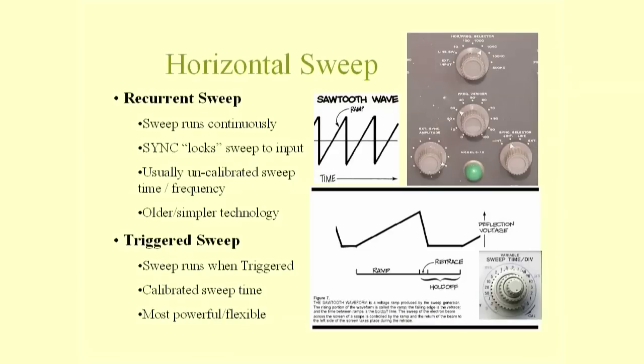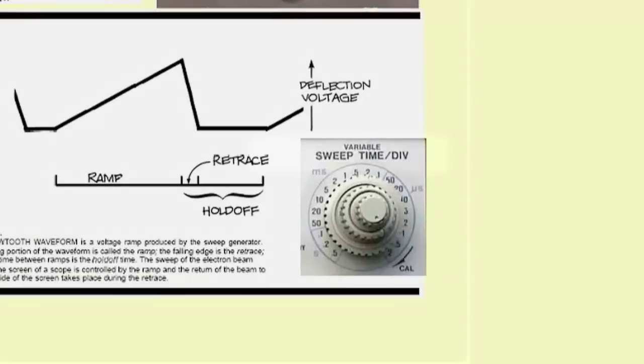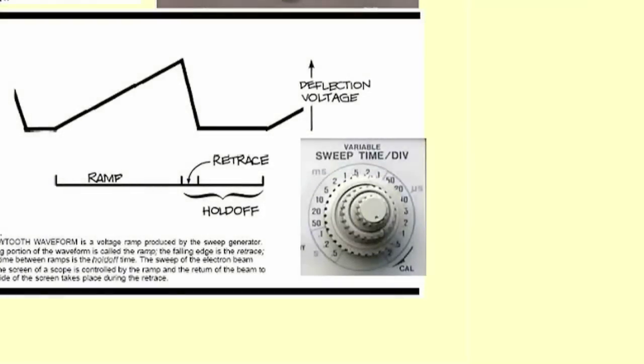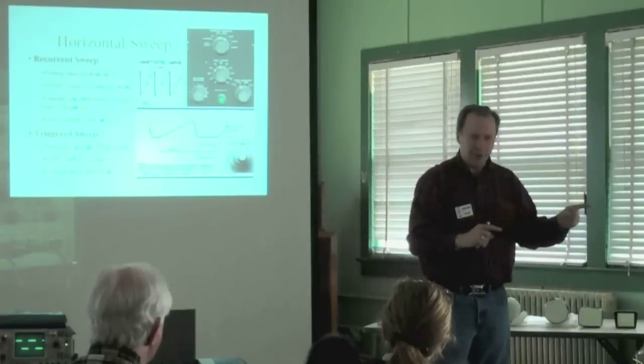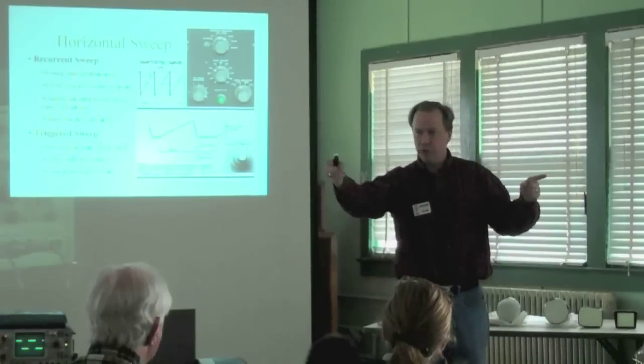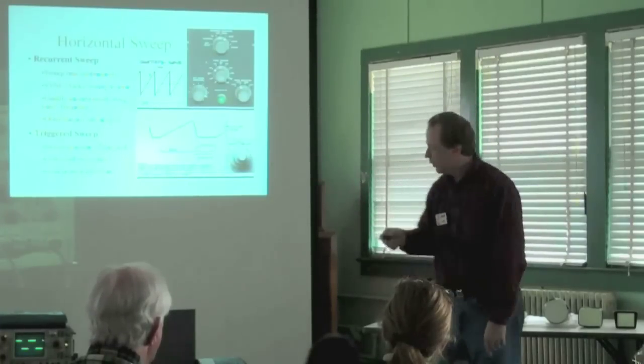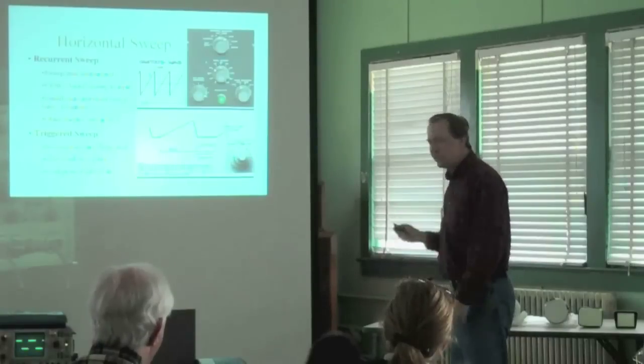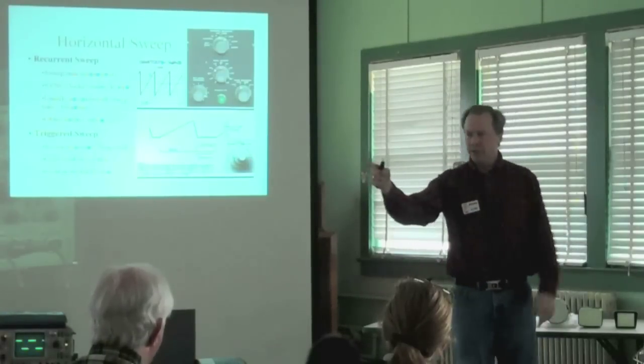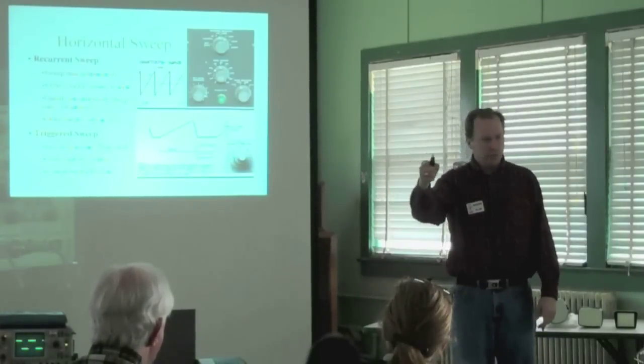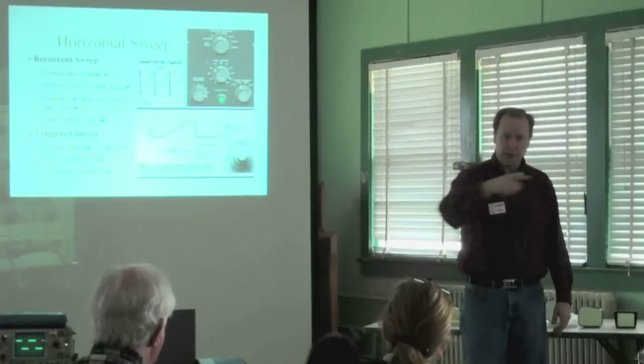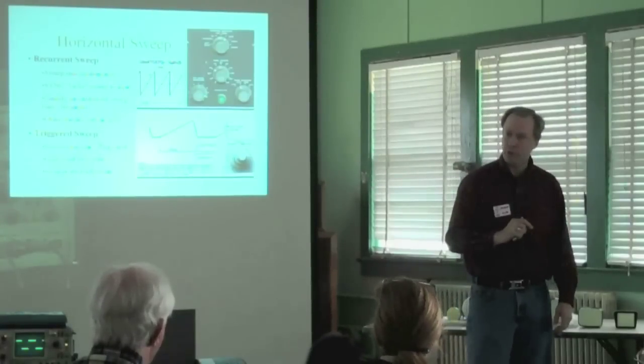So you'll see the controls in a couple. When we look at some of the scopes, you'll see some of the different types of controls. You'll typically see sweep time per division. Now, what this tells you is not how long it takes the beam to get from one end of the screen to the other. It's how long it takes for the beam to reach each division as it goes across. So if you see, say, 2 milliseconds per division, that means it takes 2 milliseconds to go one of those divisions, and you've got 10 divisions across the screen, so it would be 20 milliseconds to go completely across.